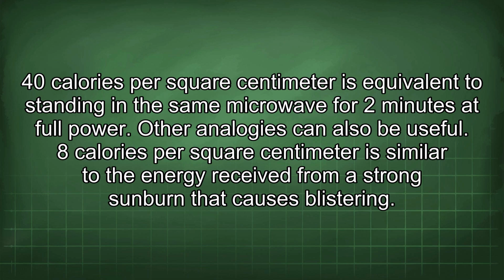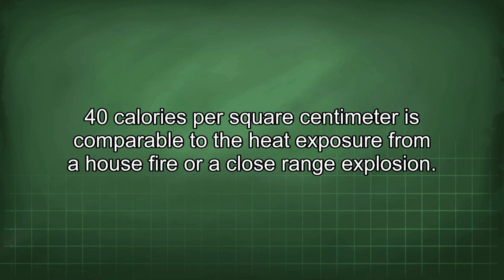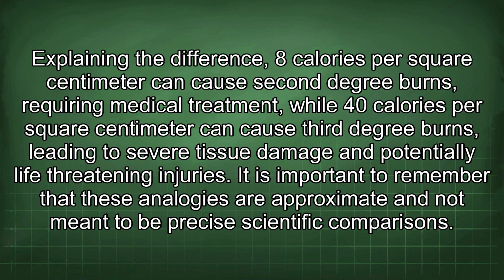Other analogies can also be useful. 8 calories per square centimeter is similar to the energy received from a strong sunburn that causes blistering. 40 calories per square centimeter is comparable to the heat exposure from a house fire or a close-range explosion. Explaining the difference, 8 calories per square centimeter can cause second-degree burns, requiring medical treatment, while 40 calories per square centimeter can cause third-degree burns, leading to severe tissue damage and potentially life-threatening injuries.